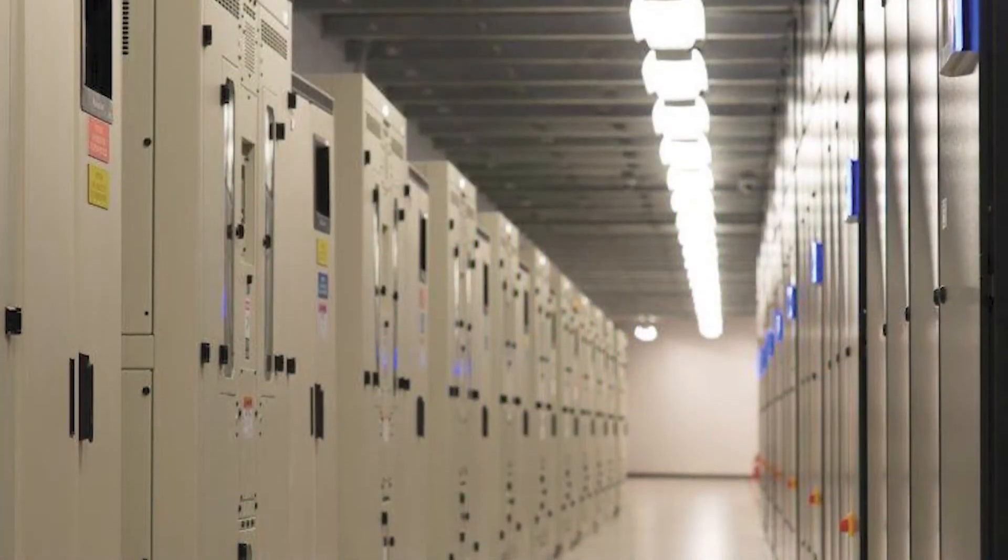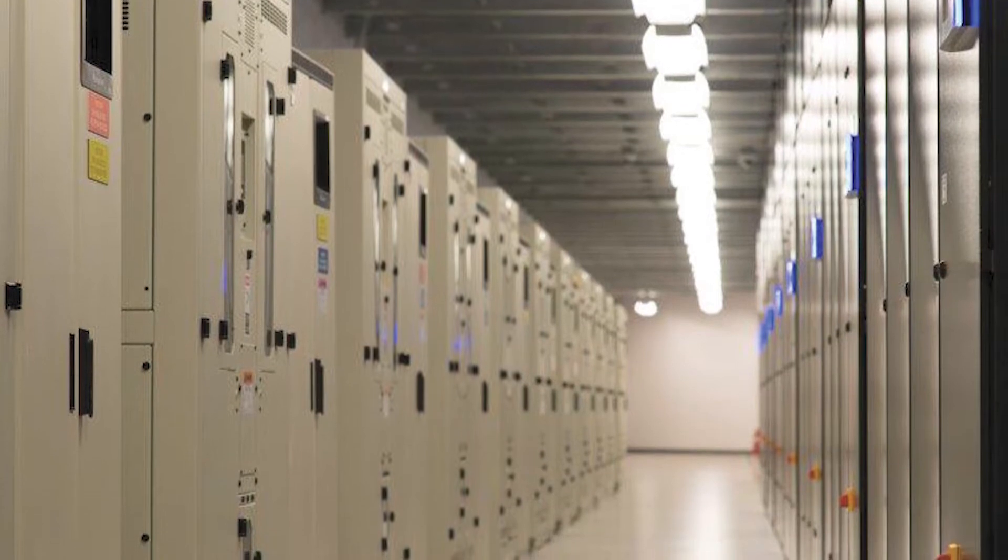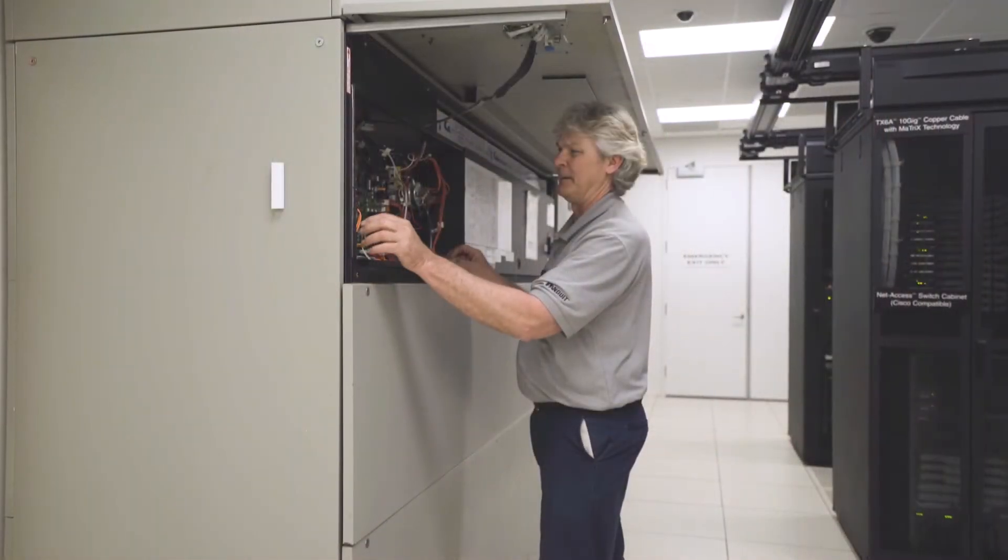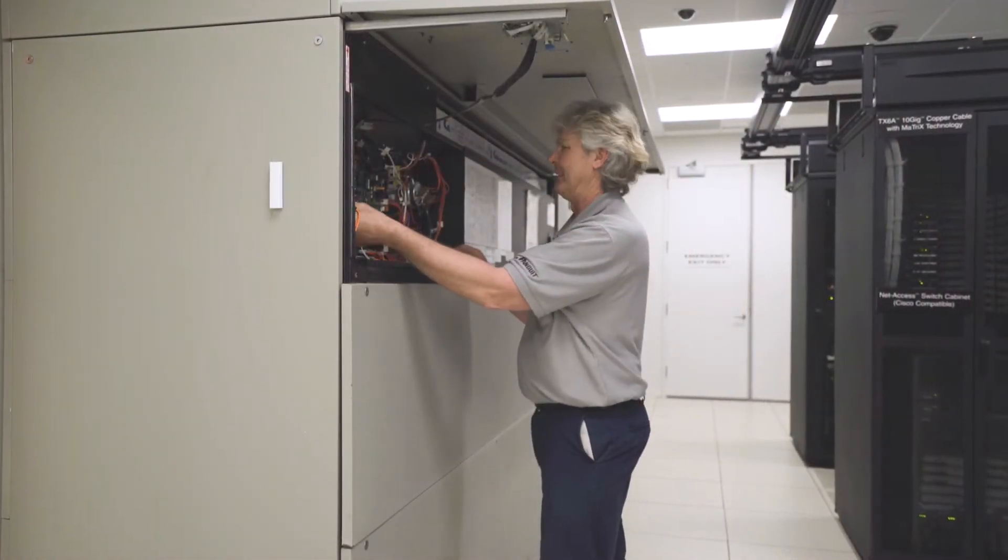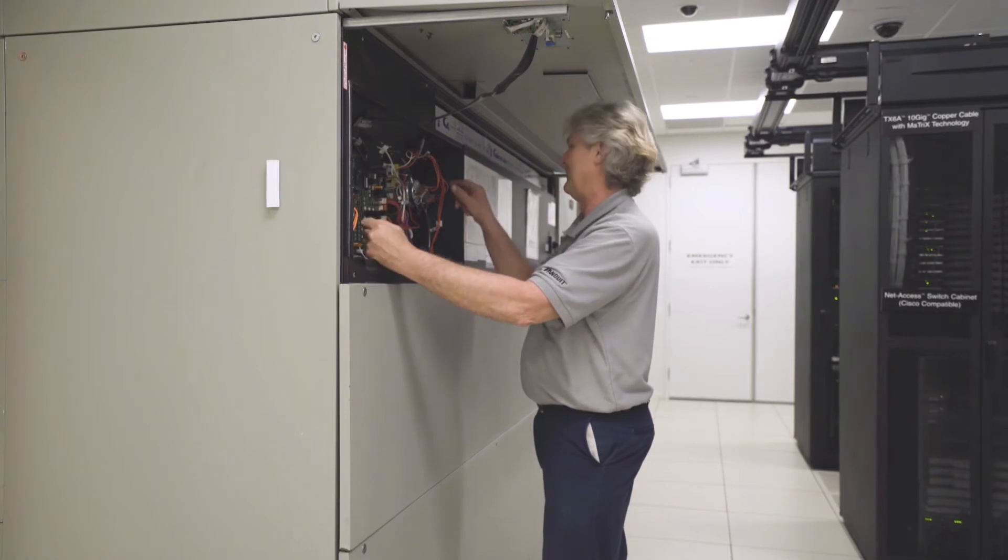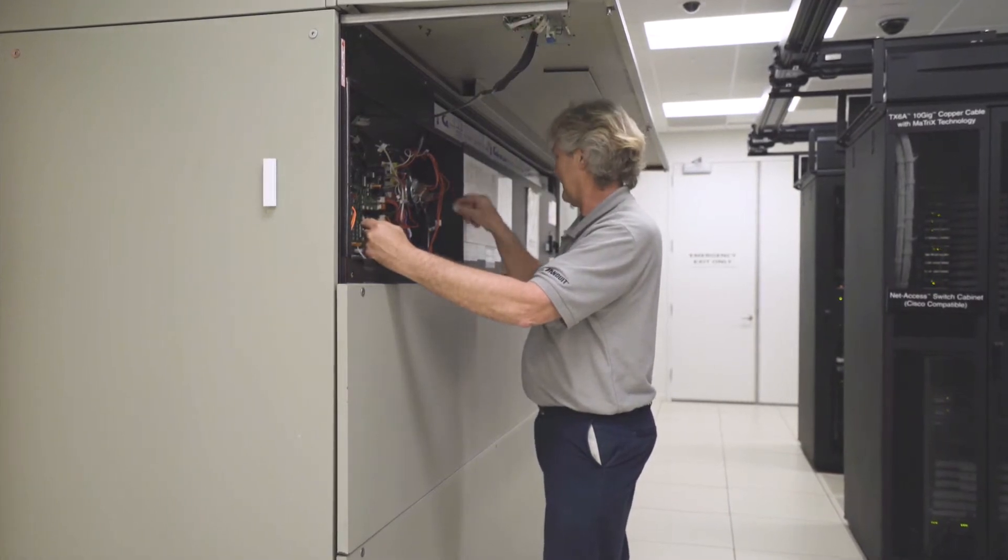The facility is equipped with 13 chilled water cooling units, but two of the units were not working properly. This was causing the other 11 units to work faster, burning more energy.